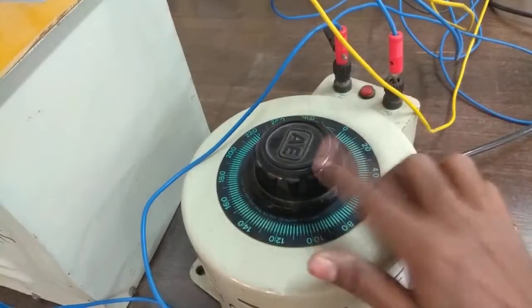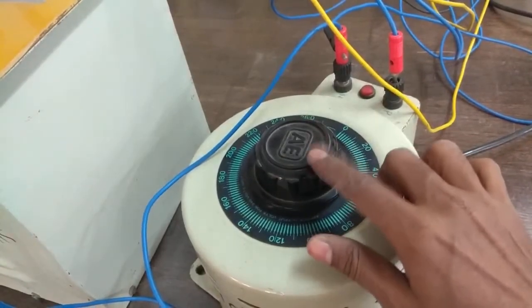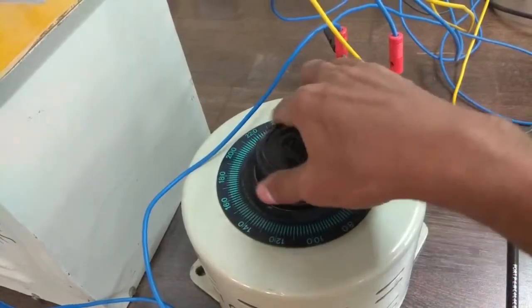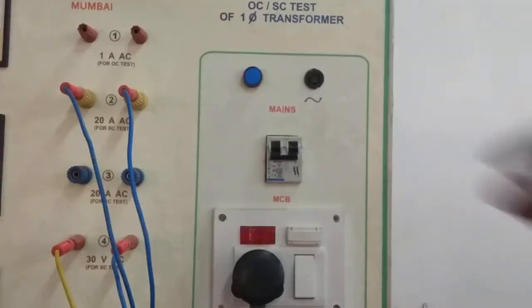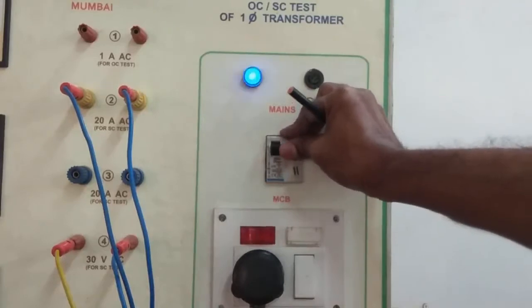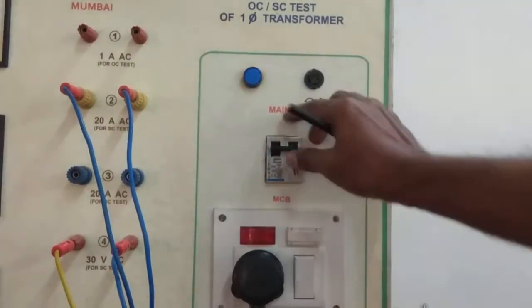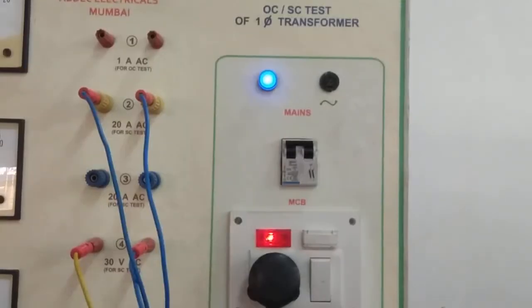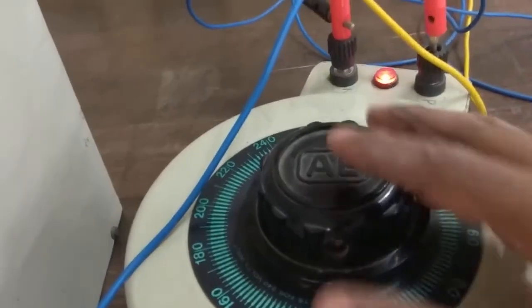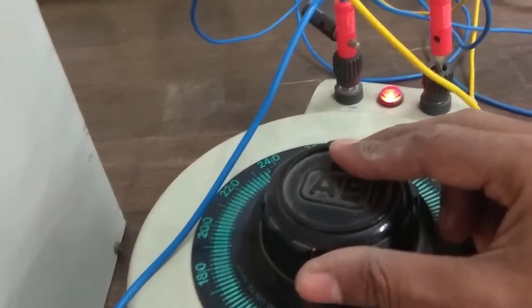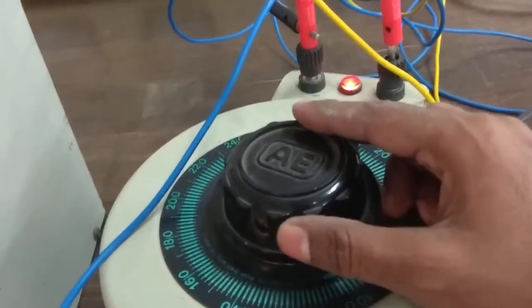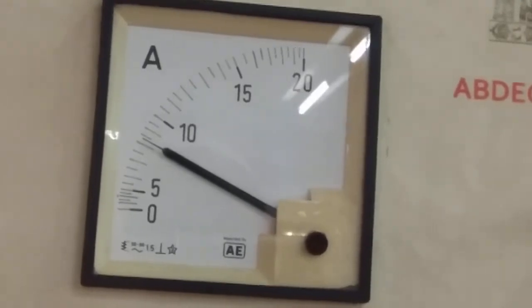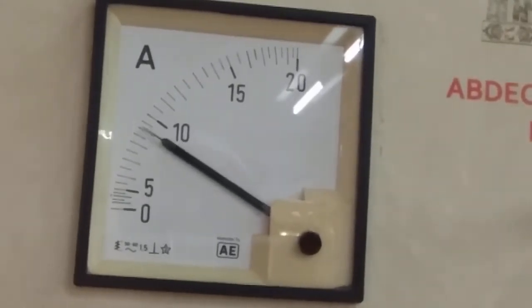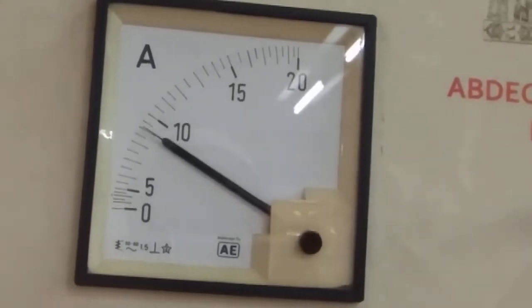First, we will check that the variac should be at the minimum position. After that, we will switch on the supply MCB and we will switch on. You can see the supply is switched on now. After this, we will gradually increase the knob of the variac to the rated current. We will bring the current to 8.9 ampere. This is 9 ampere. This is the rated current.